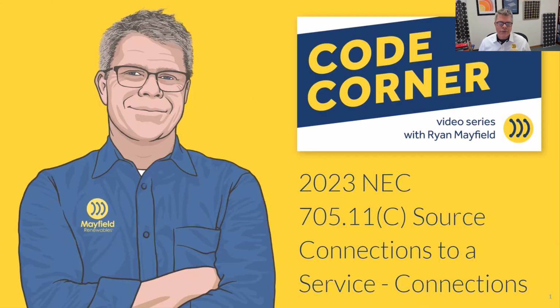This is a video series we do at Mayfield Renewables where we talk about codes and standards as they relate to the solar and solar plus storage industries. Today I'm going to dive into the 2023 National Electrical Code and specifically 705.11, which is source connections to a service. So that's the title of that section, which was actually a change in the 23 code from 2020. And then even more specifically in this video, I'm going to talk about subparagraph C, which is connections.